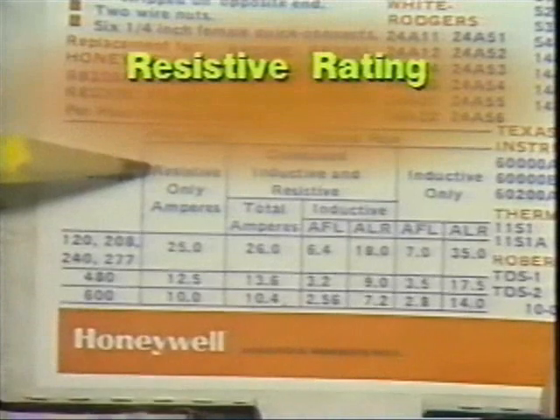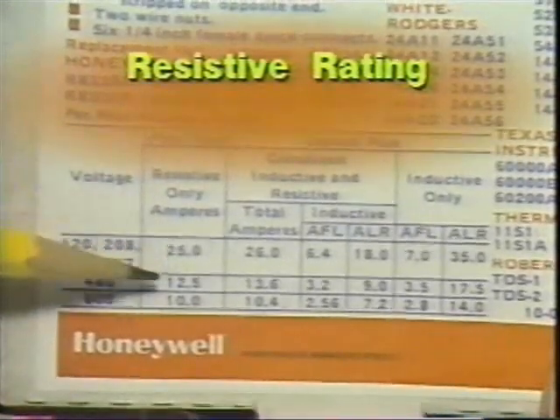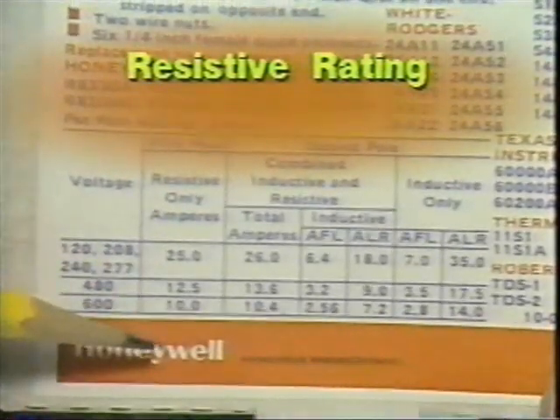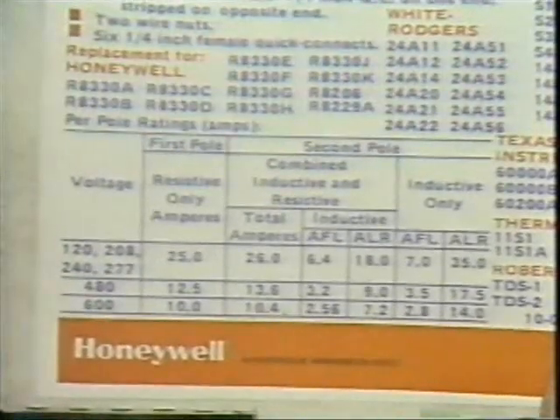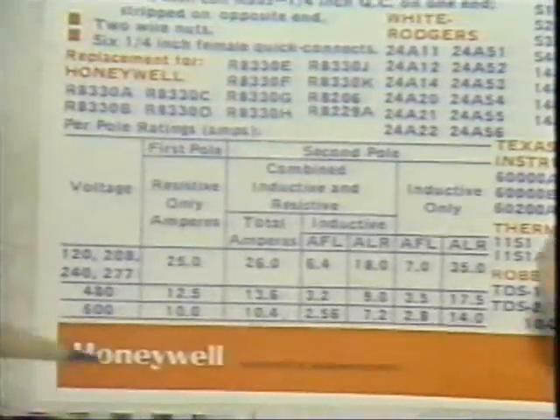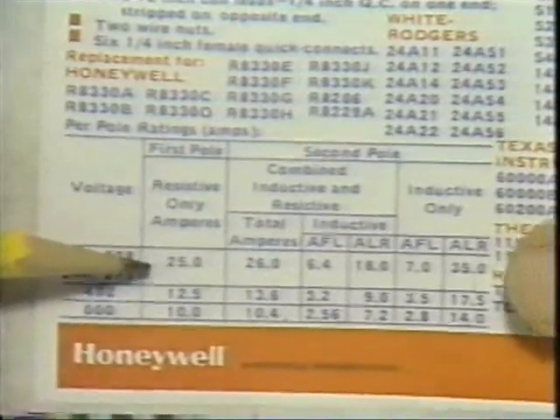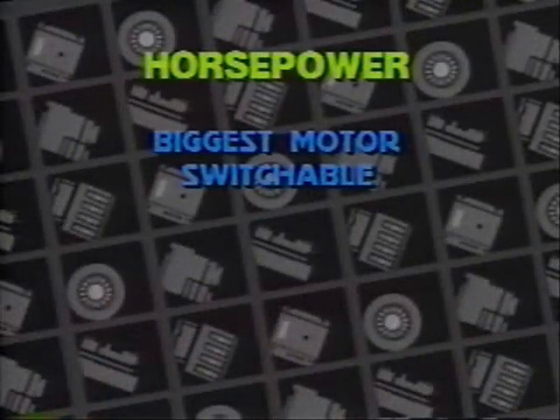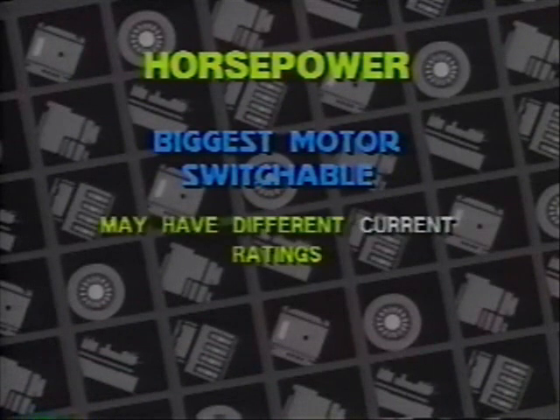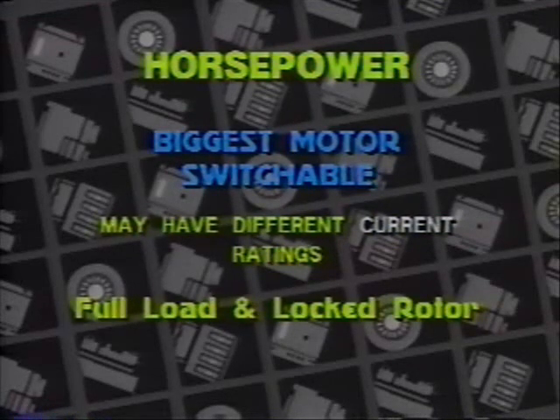The resistive rating tells how many amps a contact can switch when controlling a resistive load, such as an electric heater. The resistive rating is normally higher than the inductive because resistive loads cause less arcing. Horsepower is the approximate size of the biggest motor a relay can switch. It's important to remember, however, that different motors with the same horsepower rating can have very different current ratings. So be sure the full load and locked rotor ratings of the motor and contacts are compatible, because they're more accurate than horsepower.